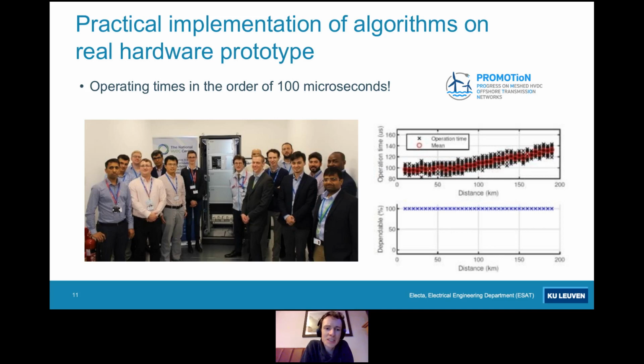We implemented the algorithms on a relay, which was hardware from Mitsubishi, and we tested it in the National HVDC Center in Scotland. You can see the picture of us standing with the relay in Scotland. The tests of the relay showed that we could achieve operating times in the order of 100 microseconds, so it is certainly fast enough.